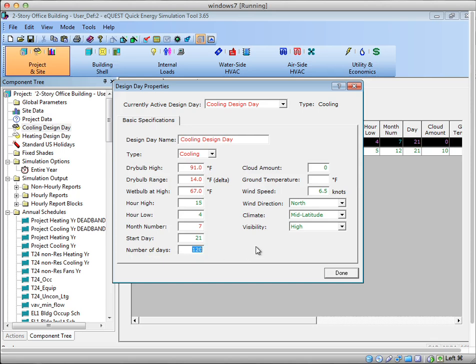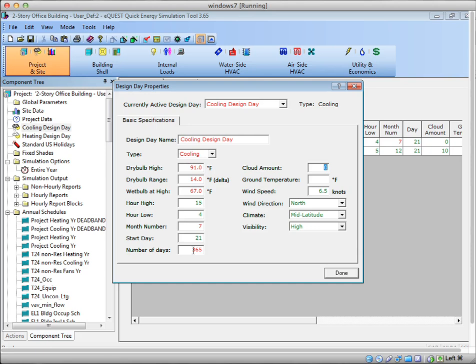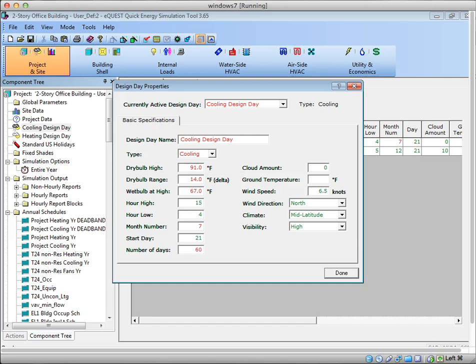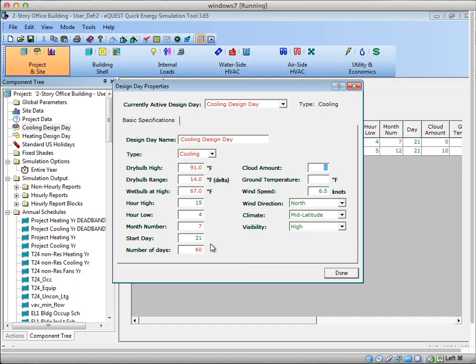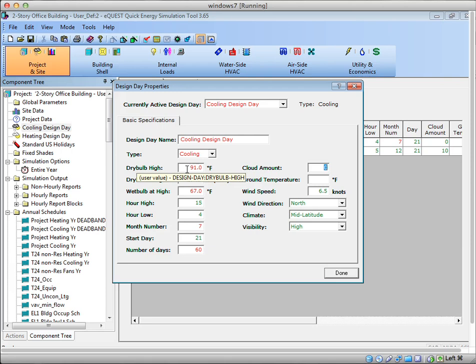If I actually change this to 365, I think eQuest might actually run and look at every single day of the year and see what day would result in the highest load. For now though, I'll leave it at 120. You might even lower this down to be 60 days. You don't need to hunt for too long. But this can be sometimes important. Not as important. I think getting the right month and the relative range to search around is about right. This is just making the model a little more accurate in sizing HVAC equipment.